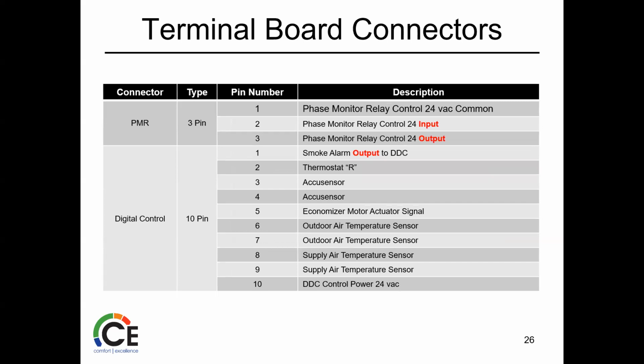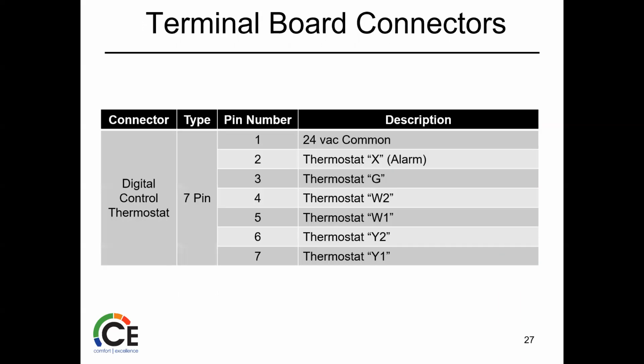Your phase monitor relay, if you have one of those, is basically just an input output situation. If it monitors something that doesn't seem right, then of course that's a shutdown spot. Your digital control, that's where your smoke alarm output is, if you're using DDCs, if you have AccuSensors, outdoor sensors, supply air sensors. So that's part of that wiring for those thermistors. Pretty simple there, right? Digital control thermostat. So it's just your thermostat connections.